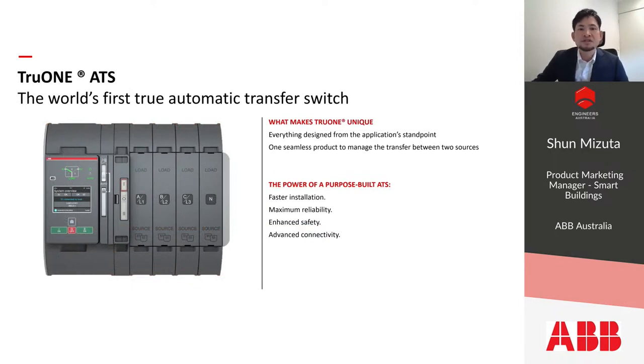Now, this is TruONE. Many of the existing solutions out there are made from components where the mechanical parts are separated from the electronics. So switches, contactors, breakers, and loose controllers, even different brands, are put together to make up one ATS, creating complicated wiring and logic. This would be a complex solution instead of fulfilling the simple need for one product that transfers the source when needed.